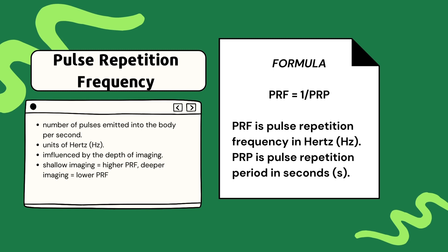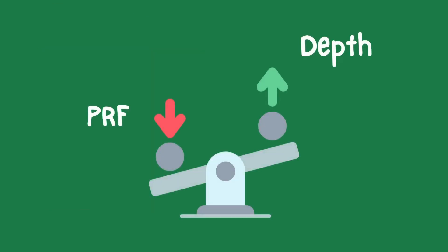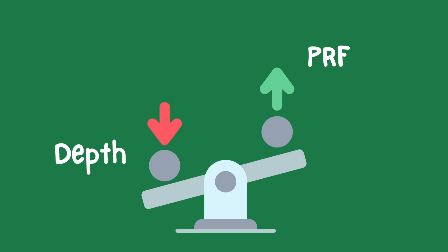Remember in our last chapter we discussed frequency and its relationship to penetration — lower frequencies were better for penetration, whereas higher frequencies were optimal for imaging more shallow structures. A similar concept applies for PRF. PRF is inversely related to depth, like a seesaw where when one variable goes up, the other goes down. When we image at increased depths, the PRF is decreased, and when we image at shallow depths, the PRF is increased.